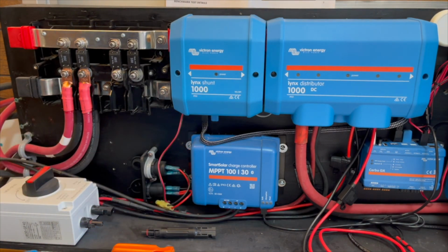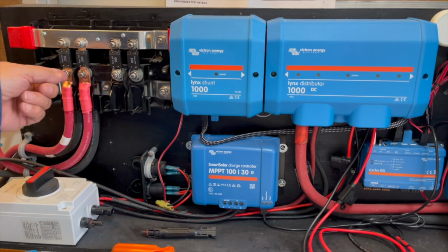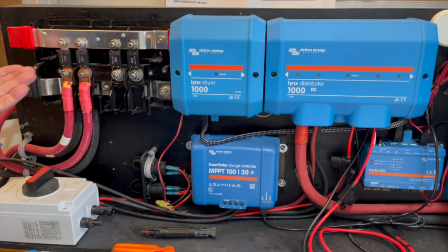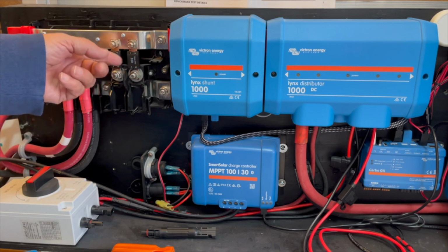The cables are 2 AWG, equal length, which is important, and I can have 4 sets of battery banks. Right now, 1 set goes to 1 battery, but I can put 1 set to 2 batteries and still maintain that balance. When you go to a third, you start losing balance, so keep that in mind.